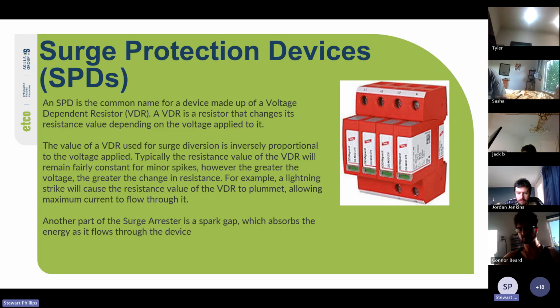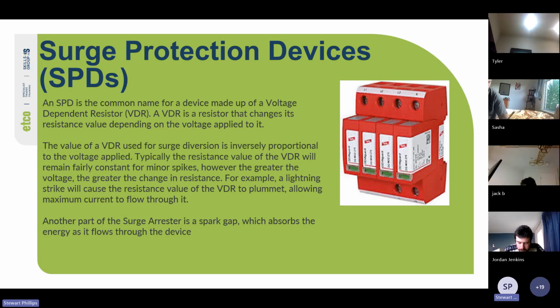The key difference: surge protectors are designed for individual appliances or small groups of electronics, while arrestors are used to protect entire electrical systems or large pieces of equipment. So it depends on the size of the equipment. A surge arrestor is a spark gap. So yeah, surge arrestor is more when you're talking infrastructure. I don't know why they've used surge arrestor there, but another part of a surge protector is a spark gap, which absorbs the energy as it flows through the device.